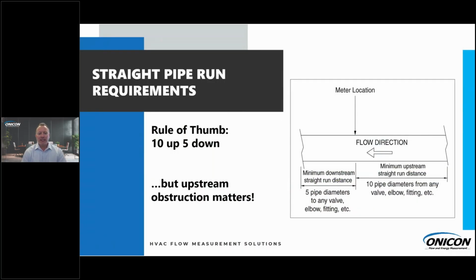I know you've heard the 10 up, 5 down. That's typically the industry standard. It's 10 pipe diameters upstream and then 5 pipe diameters downstream. What they don't tell you is what that upstream obstruction is. So if you hear the 10 and 5, for our flow meter to achieve that 1% accuracy plus or minus, that's actually followed by just a 90-degree bend with roughly 10 pipe diameters of straight run. So definitely the upstream obstruction is critical.